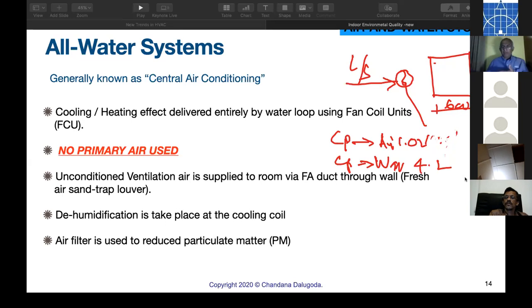In every zone you have a fan coil unit. That's the all water system. Of course, for a large auditorium or a meeting place, slightly larger places, we can have a mini AHU or AHU. But basically, the all water system is chilled water piping with fan coil units. Dehumidification takes place in the cooling coil in the room. Unlike air and water systems, there's an air filter, and fresh air can be supplied to the zone.